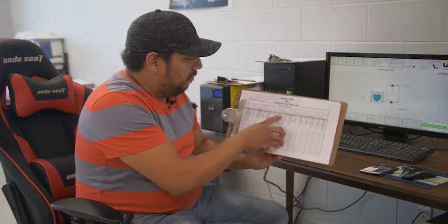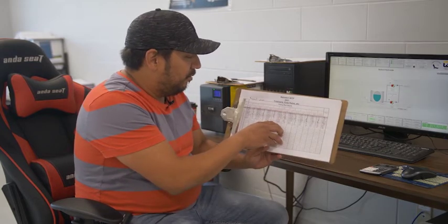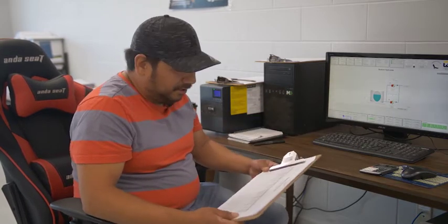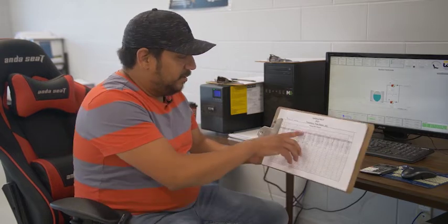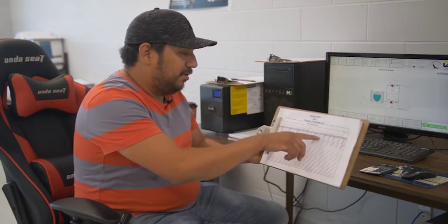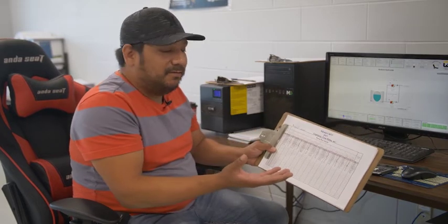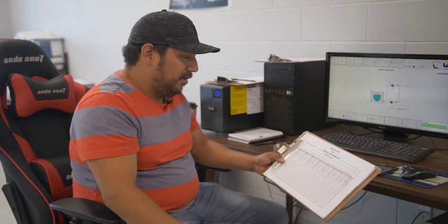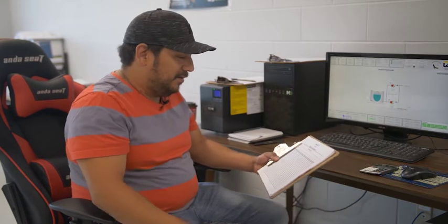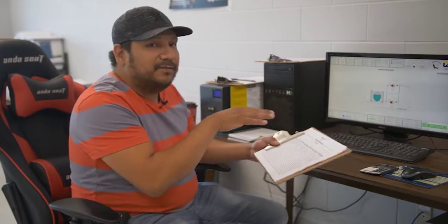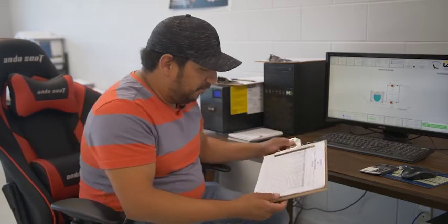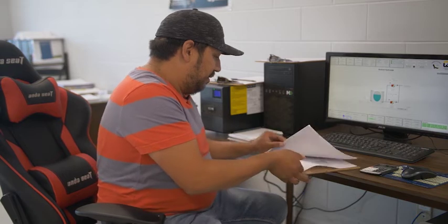Transmission pump. Well, we know transmission pump 1404 is our lead pump, and that one is always going to be running regardless, because the transmission line needs to maintain pressure. But if we notice something out of the ordinary on the other transmission pump, which is what we call the lag pump, if that's been running 24 hours, then obviously that's going to set off an alarm in my head, and usually tells me that there might be a leak or there's something going on with the set points of the pressure, that sort of thing. So we monitor that for that reason as well.